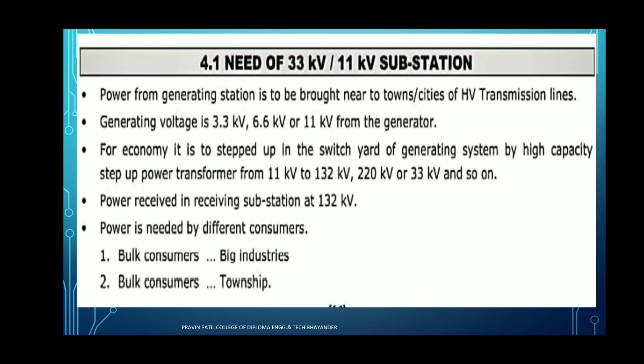Then power is received in the receiving substation at 132 kV substation. Power is needed by different consumers, bulk consumers, big industries and bulk consumers for the township. So these are the needs of a 33 by 11 kV substation for supplying the electric power. For the economy, it is stepped up in the switchyard of the generating system with the high capacity step up power transformer of 11 kV to 132 kV or 220 kV or 33 kV, etc. The power receiving substation is the 132 kV substation.